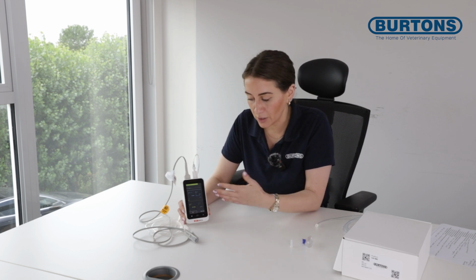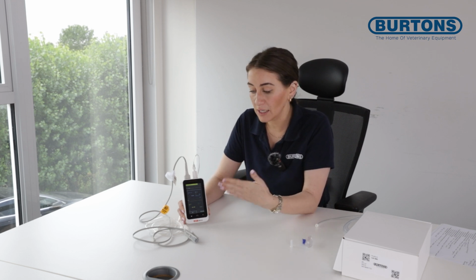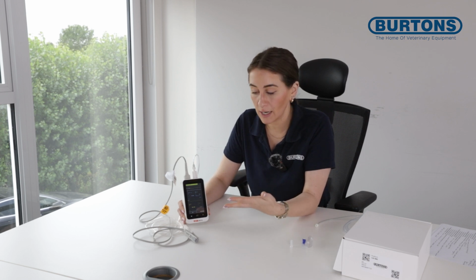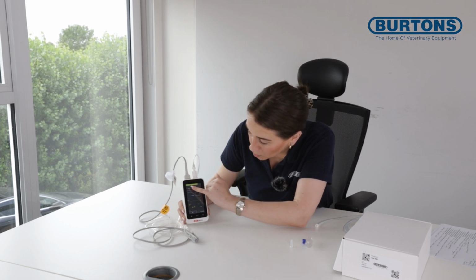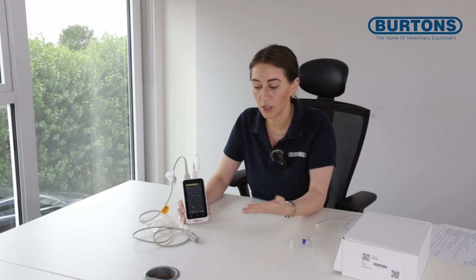the heart rate is higher than we would expect or want, or the respiratory rate is higher or lower, etc. So that's the physiological alarm, and that's referring to presumably your patient. And then we have a technical alarm, where the machine is not functioning as it should due to a technicality, and we have that error at the moment, for example SPO2 sensor off. So that's not a physiological issue with our patient, it's actually a technical issue because the SPO2 probe isn't measuring tissue within it.